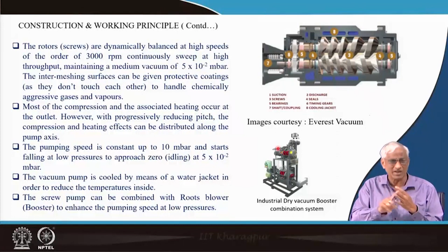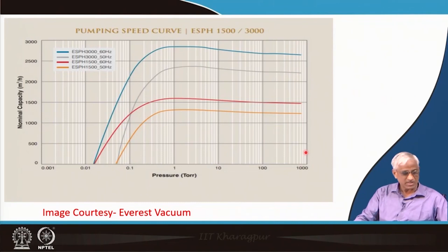So these things have to be taken care of, and most of the pumps are quite rugged, I would say. They can give sufficient pumping speed and a fairly good amount of vacuum, not just 1 torr and all. But if you want to go to molecular distillation etc., you can add roots blowers. So this way, by combining pumps or combining accessories like heat exchangers, filters etc., you can utilize the screw pump in a variety of applications. What are those applications?